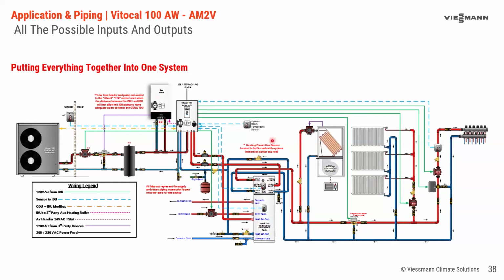Now, we're going to look at a couple of things we didn't examine. The first is the room temperature sensor. This is optional. If you had a house where there was a common area in which the thermostat was a good reference point for the building's temperature, and there wasn't a lot of controls on the radiators, so there wasn't zoning every room. If you had a zone in the room where the thermostat's in, obviously there's going to be a conflict there with this heat pump making heat when the thermostat is closing and opening valves. So this would be in a system where you already have a central thermostat, and you want to know the room temperature so the heat pump can maintain the buffer tank temperature based on room temperature.